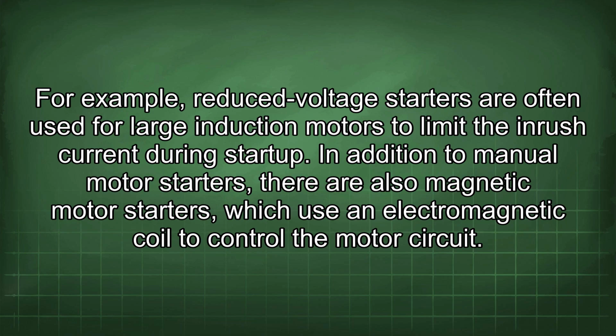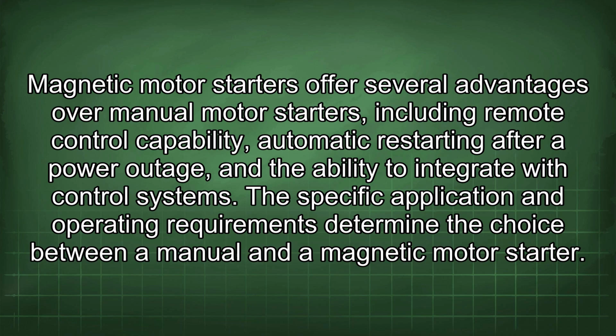For example, reduced voltage starters are often used for large induction motors to limit the inrush current during startup. In addition to manual motor starters, there are also magnetic motor starters, which use an electromagnetic coil to control the motor circuit. Magnetic motor starters offer several advantages over manual motor starters, including remote control capability, automatic restarting after a power outage, and the ability to integrate with control systems.